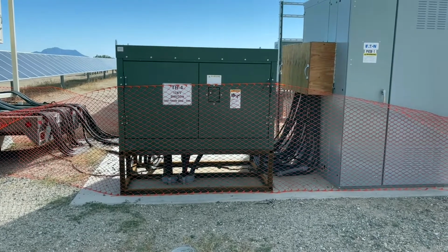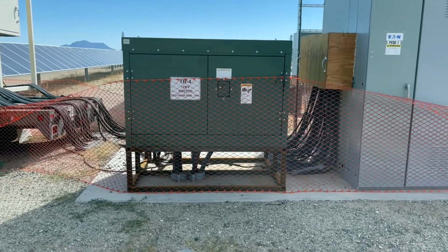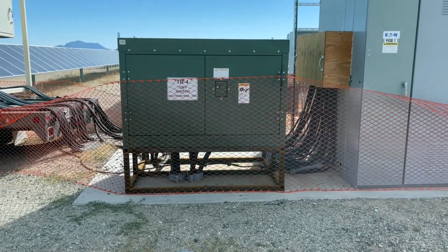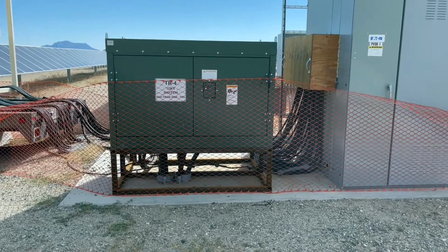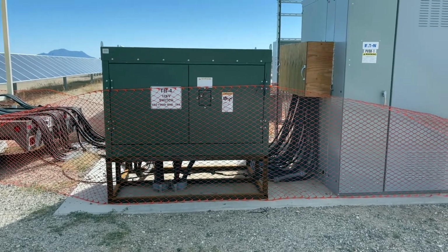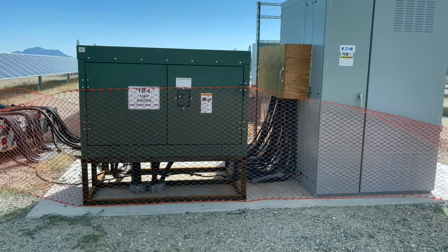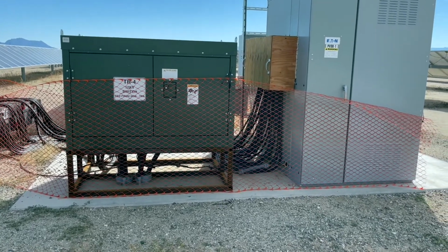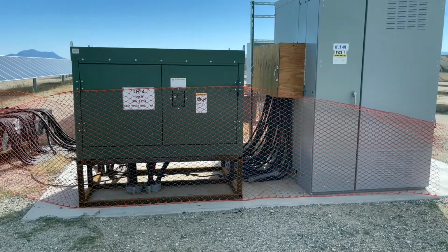Those are the 12,000 volt cables. This medium voltage switch has big mounts for the elbows. The same elbows that used to bolt to the transformer are now bolted inside this switch, and they raised the frame up. See the frame? It's raised up.